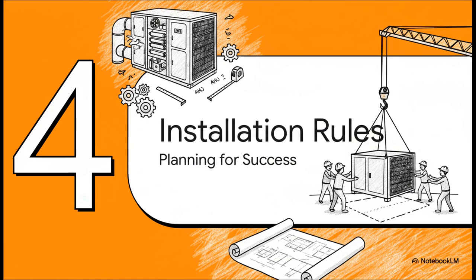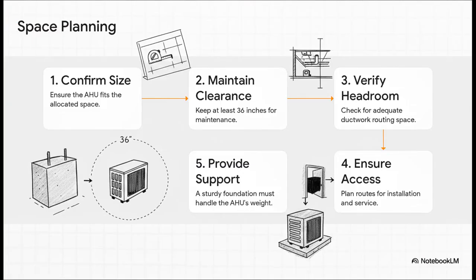So we've designed it, we've selected it, now we have to actually install this massive piece of equipment. And let me tell you, planning the space properly is absolutely critical for the success of the whole project. Here are 5 non-negotiable rules for space planning. 1. Double and triple check your dimensions. 2. You absolutely must leave at least 36 inches of clearance all around it for maintenance. 3. Make sure you have enough headroom for all the ductwork. 4. Plan your access route. How are you even going to get the machine into the building? And 5, make sure your foundation can handle the weight. I promise you, get any one of these wrong and you are in for a world of pain.